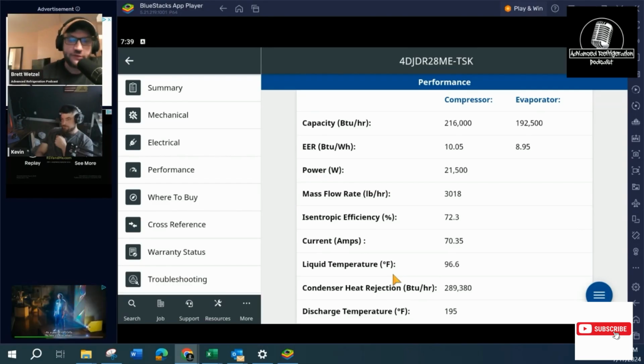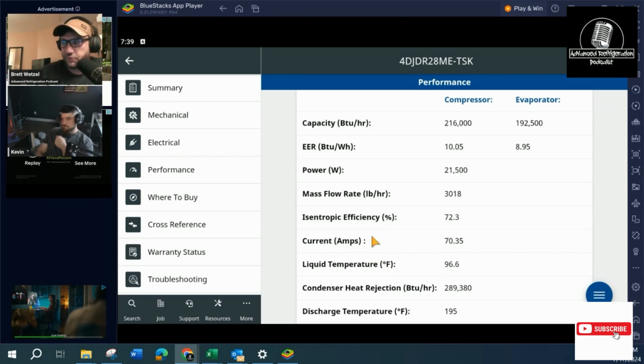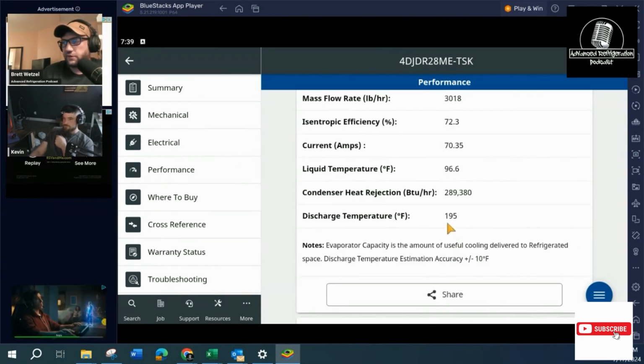Sensible heat, the actual heat that's added to the refrigerant from the compression process. And then it's actually, like Kevin said on the other app, giving you the 195 degree discharge temperature.